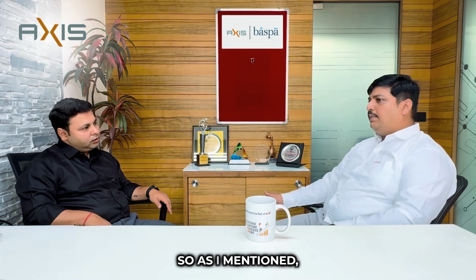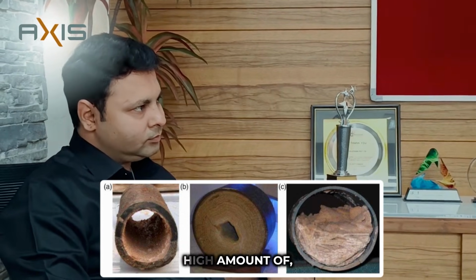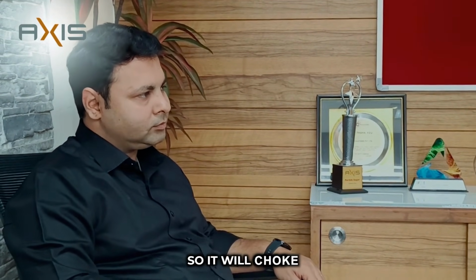As I mentioned, if we are not putting in the SWAS system, we have no idea what impurities are going into the water and steam to the turbine blades. Sometimes it will clog the boiler tubes if there is a high amount of silica or high conductivity. Due to the corrosion effect, it will also damage the turbine blades. Maintenance of the boiler, particularly the turbine, is very difficult. If a power plant needs to shut down, that is very critical because of the damage to the turbines and turbine blades.